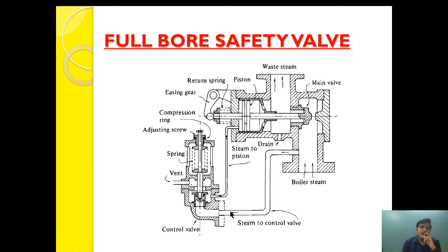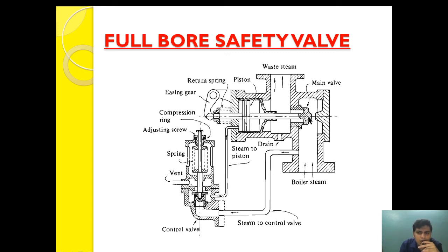Once the pressure exceeds the design pressure limit — i.e., 3% above the working pressure — the steam will act on the control valve surface and lift it against the spring. As it lifts, it finds a passage and this steam goes on to act on the operating piston area. The operating piston surface area is almost twice to four times that of the main valve area. Since force equals pressure multiplied by area, the force generated by the steam pressure on the piston will be much higher, pushing the piston in the opening direction.